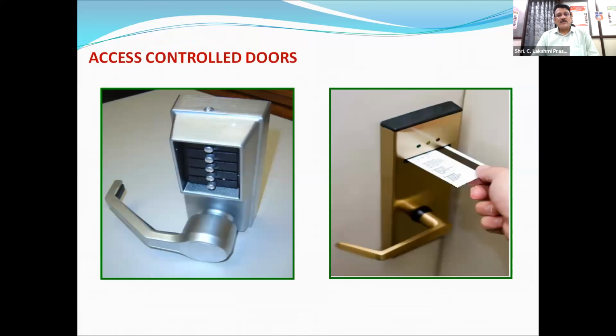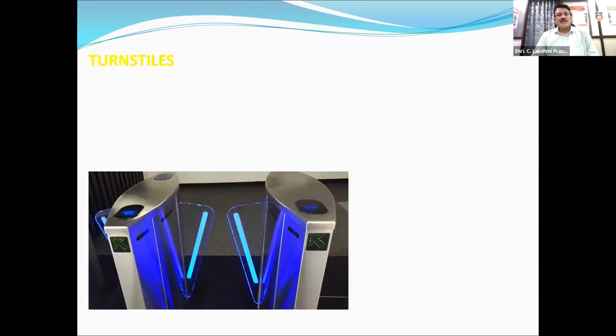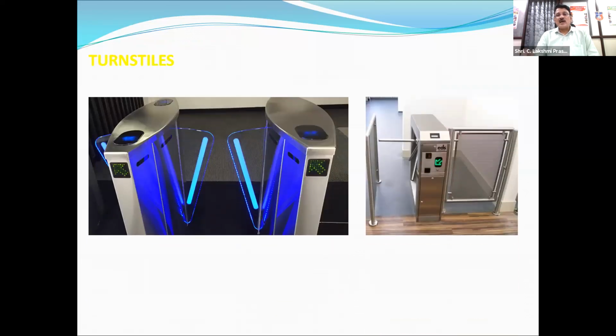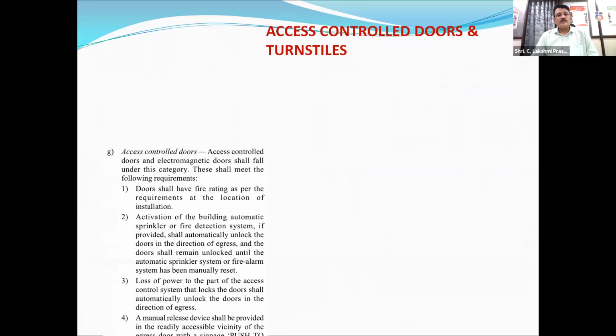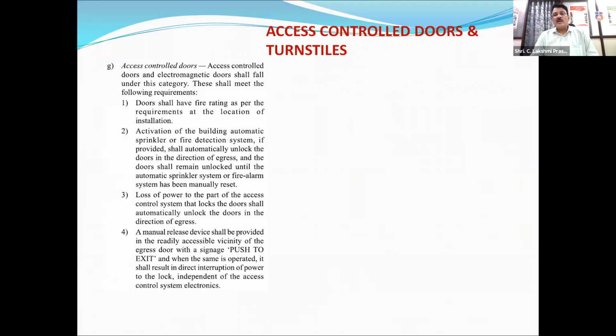Then access control. Then turnstiles. Even turnstiles are supposed to have a normal one for emergency evacuation purposes. Access control, I have already told, in offices wherever there are access control doors provided, they should be deactivated the moment there is a fire alarm, because otherwise it will lead to this much rush at the doors. If everyone has to show their ID card and get out, it is not possible.